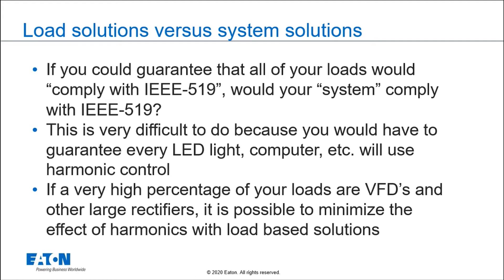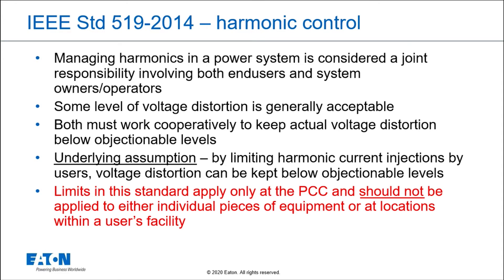What if you tried to protect all your loads by correcting harmonics on the loads themselves? It turns out IEEE 519 is a system approach, not a load-based approach. You would have to guarantee that every LED light, every computer, every variable frequency drive — anything that creates harmonics — would have to have harmonic control on it. If a very high percentage of your loads are drives and large rectifiers, it's possible to minimize harmonics with load-based solutions. But if you have a blended load throughout the system, it's going to be difficult. So think about how to comply from a system level versus individual load level.